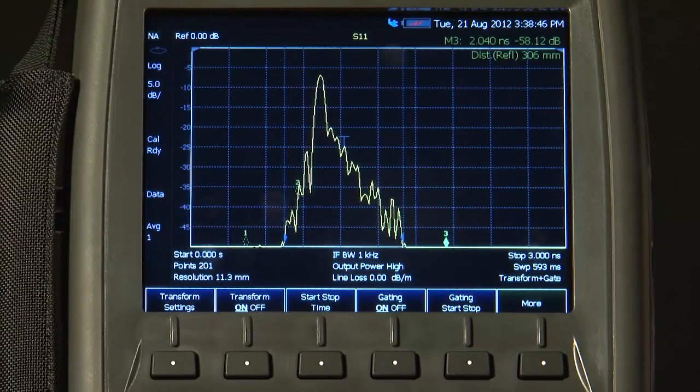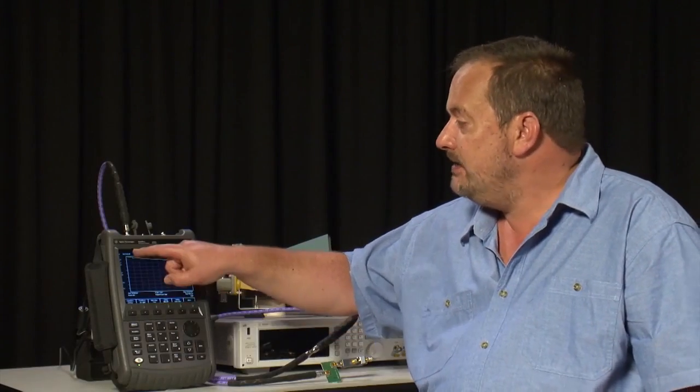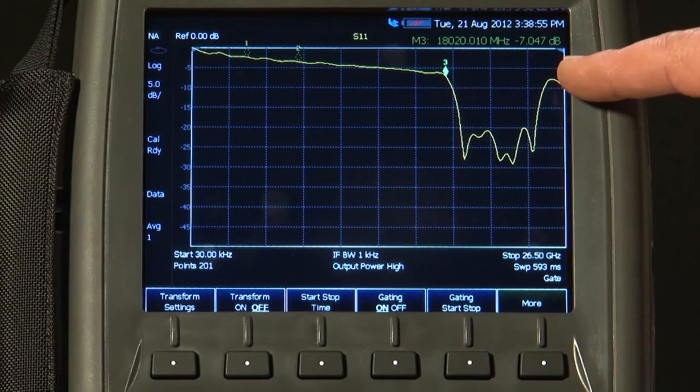So if I now turn off the inverse Fourier transform, but I will leave the gating on, you'll see we are back in frequency domain again, but much of the ripple on the trace has now disappeared.